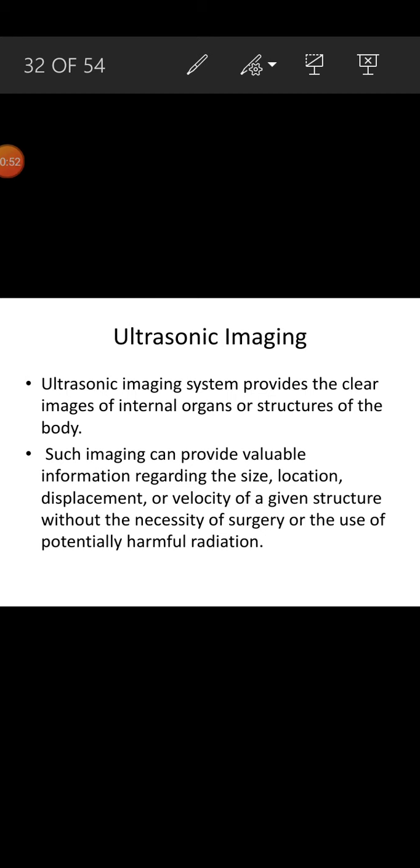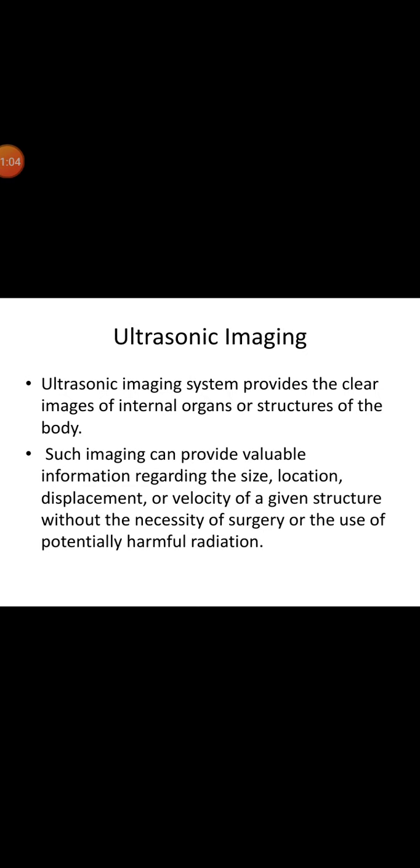Instrumentation must include an electrical signal source capable of driving the transmitter, which consists of a piezoelectric crystal, and the same crystal can be used for receiving echoes, or a second crystal may be used. After amplification, the received information is displayed in one of several display modes.